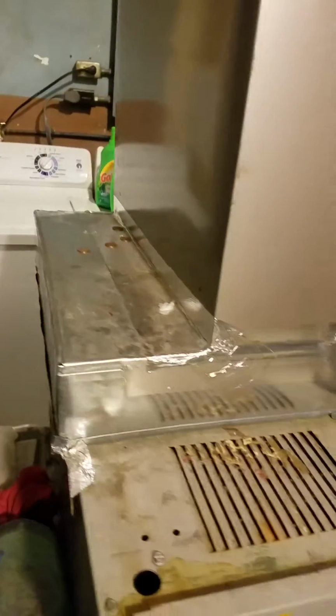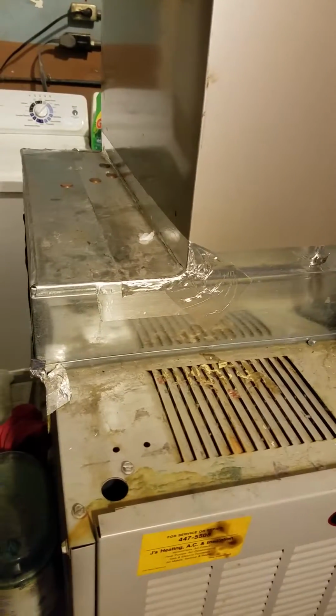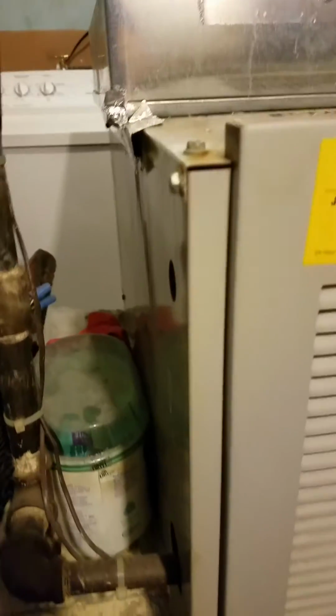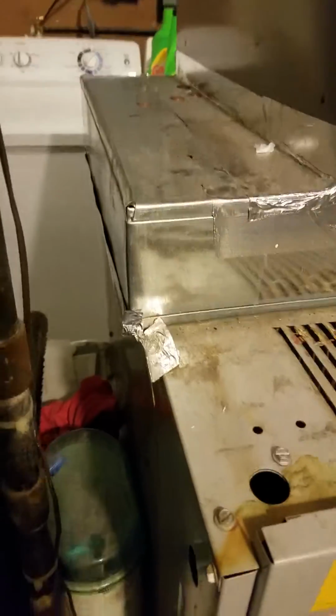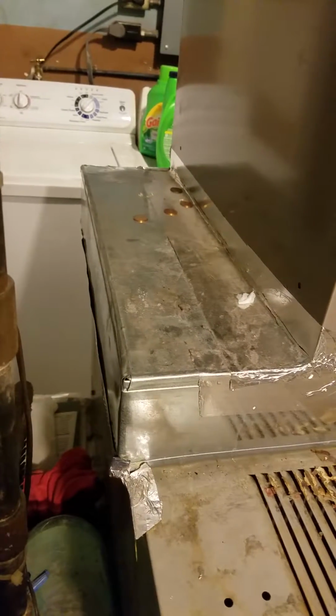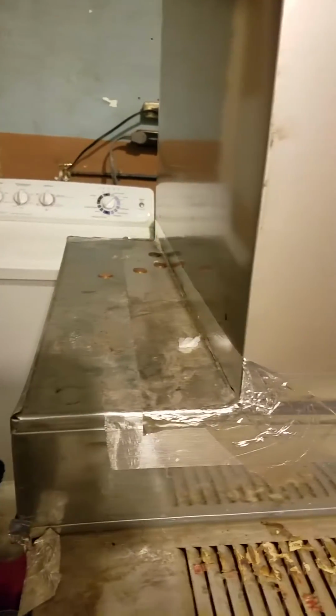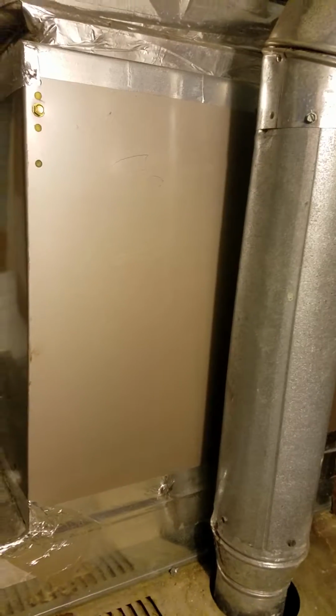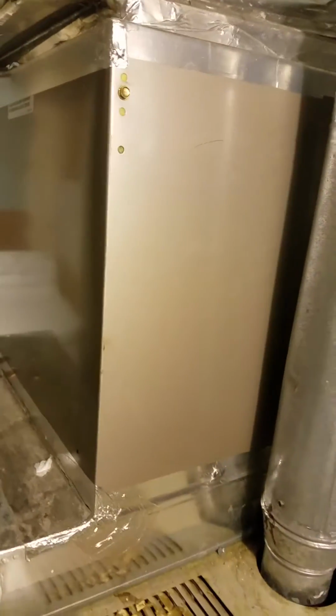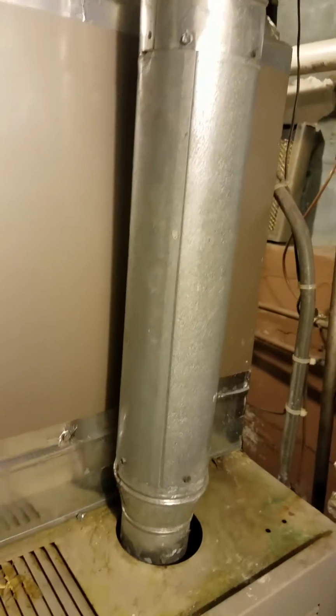But I want you to kind of see this. Here's a base that actually is an overhang on the side of the furnace going this way. It's about 4 inches tall, about 21 inches long there. And then here's your coil. So from this corner to the coil, there's about 6.5 inches of offset, which largely could have caused this problem with his heat exchanger having the hot spots. There's no doubt in my mind that that's what happened.